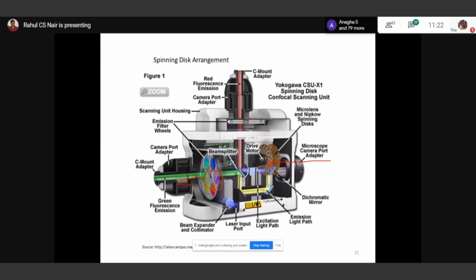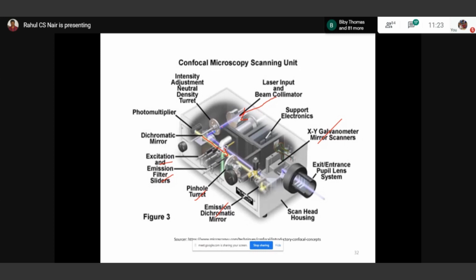These are the filter sets, and this is the light path, and this is the camera port, right? Another arrangement is the confocal that we have already discussed. This is the raster scanning type confocal unit. Like I said, the laser is coming through this point. This is the input port, and from there some kind of intensity adjustment is there. Then a dichroic mirror deflects it for excitation, and there are different filters: excitation filter and emission filter. Then there is the pinhole turret, then various types of mirrors and galvanometric motors for position control. This entire unit will come as a box that can be placed near the microscope.